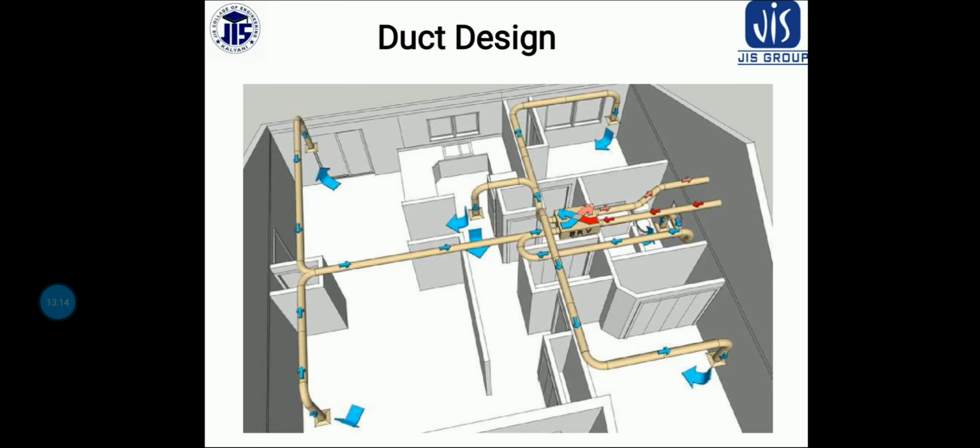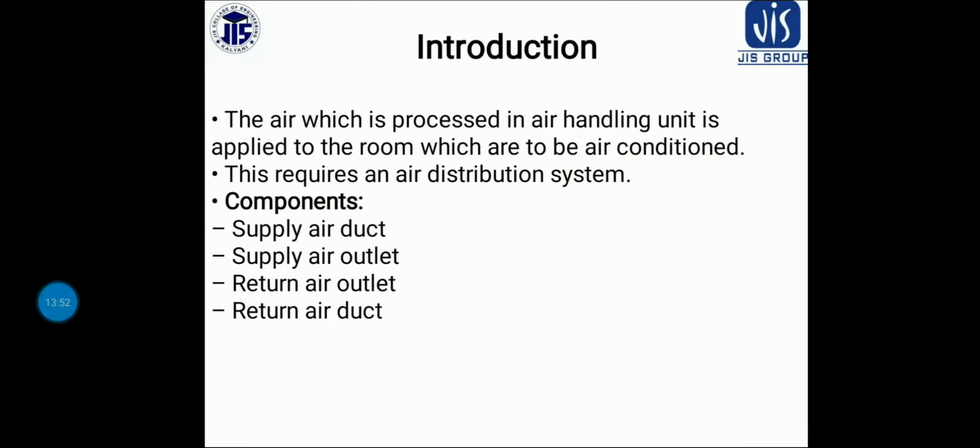Next point, the rectangular duct aspect ratio should be kept within 4:1, as a higher aspect ratio can create turbulence. We need to have some square shaped duct, so that the aspect ratio would be 1:1, and this duct is desirable for better efficiency. So this is all about the construction and the joints, and some points about ducts which we need to remember.